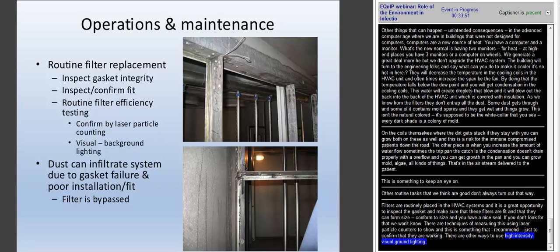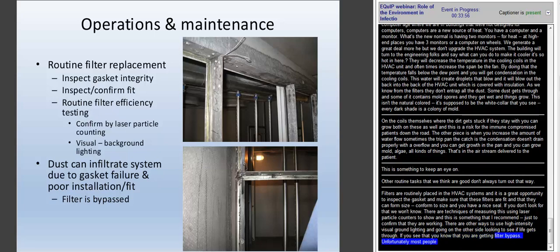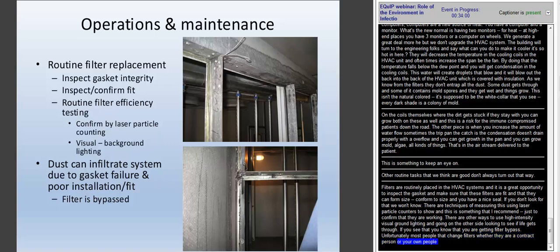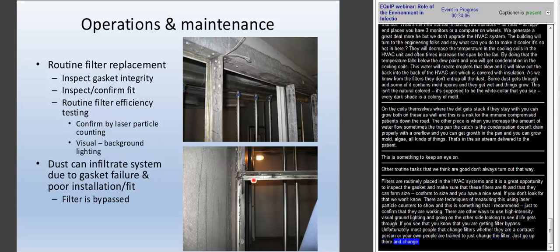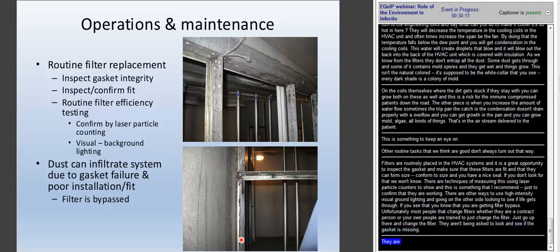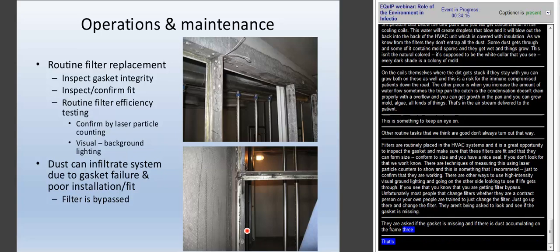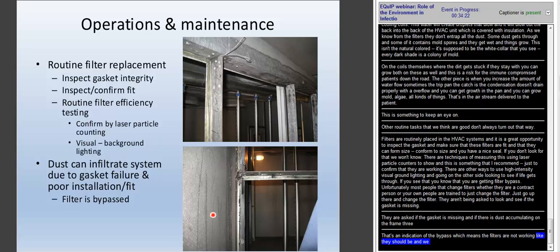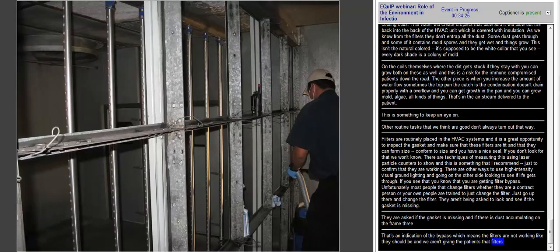Unfortunately, most people that change filters, whether they're a contract person or they're your own people, they're trained to just, quote, change the filter. Just go up there and change the filter. So they're not being asked to look to see if the gasket is missing. They're not asked to look: are we missing a gasket, and are we seeing dust accumulating on the frame like we do here? That's all an indication of bypass, which means the filters were not working like they should be, and we're not giving our patients the type of filters they're supposed to need. So this is something that really needs to be done, in my opinion, on a regular basis.